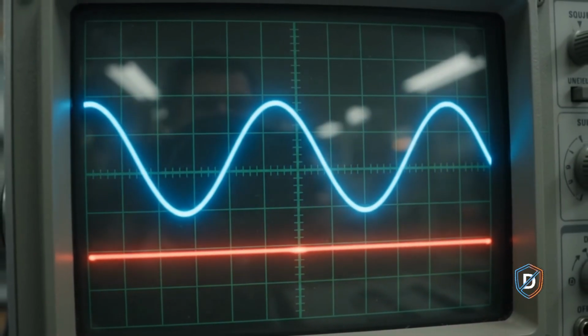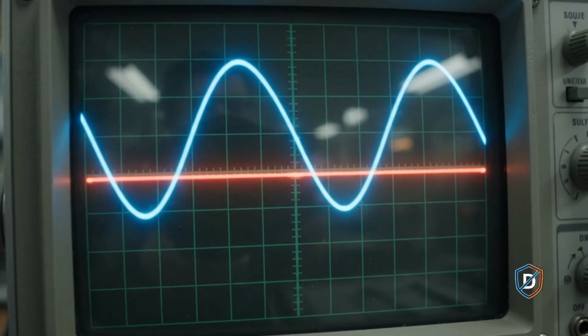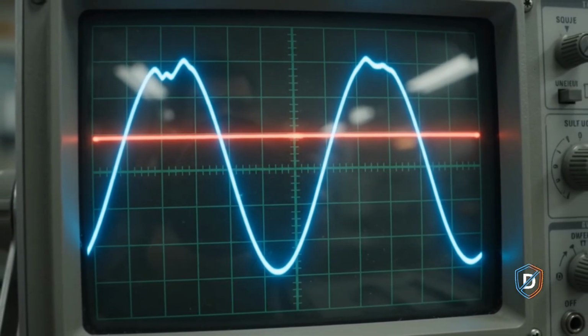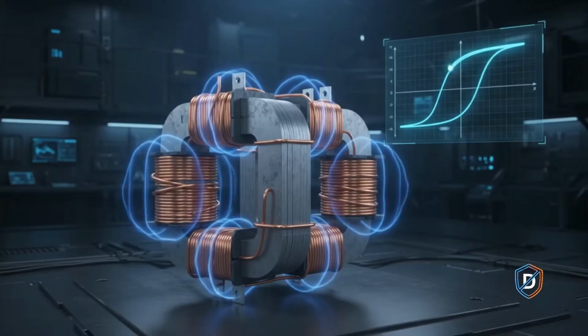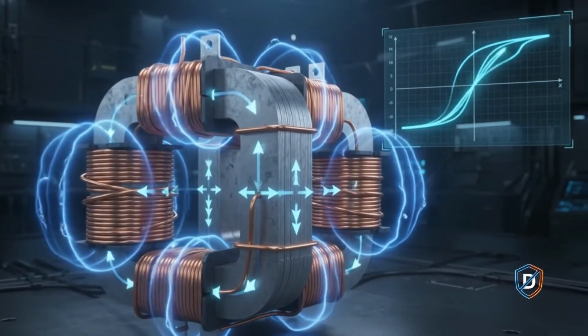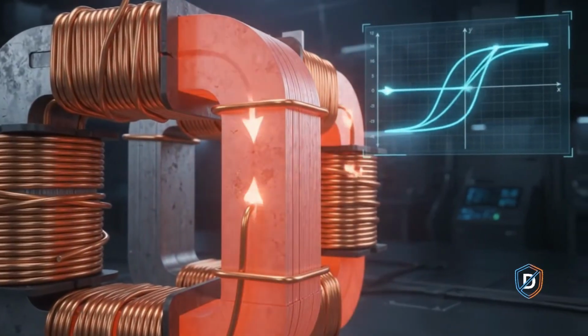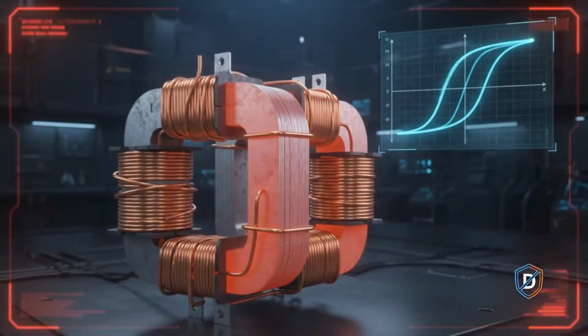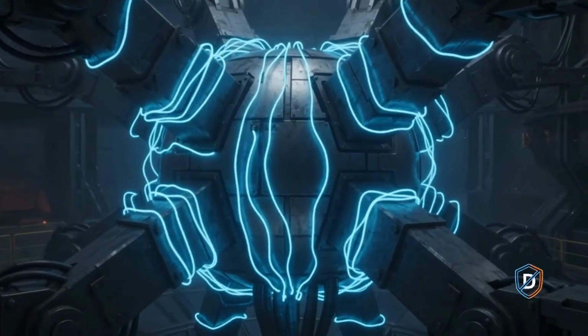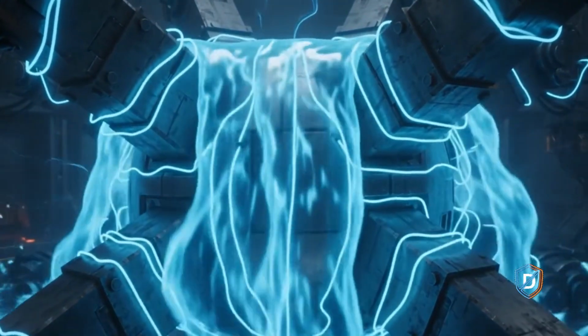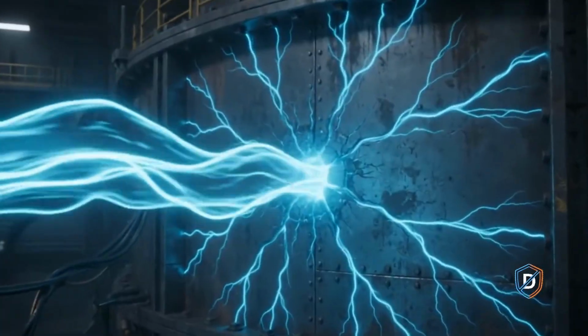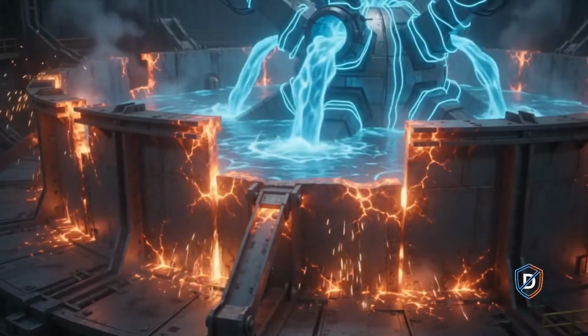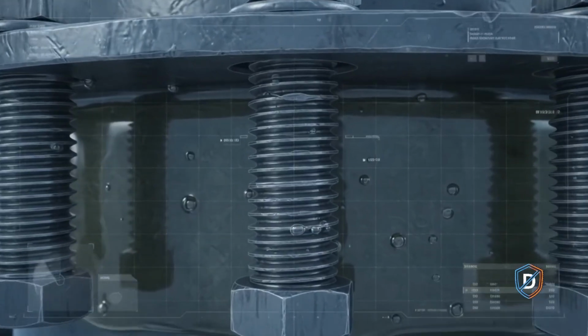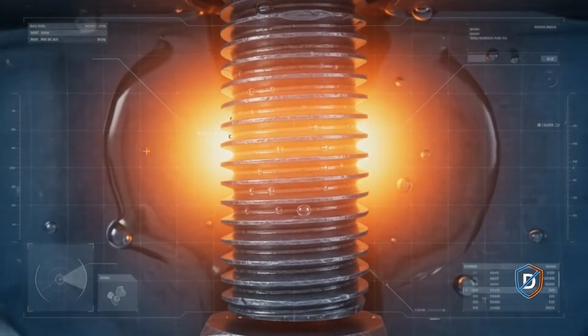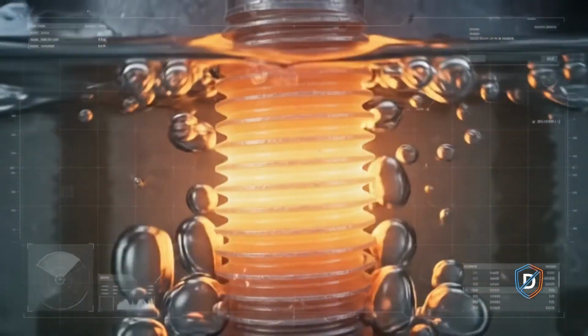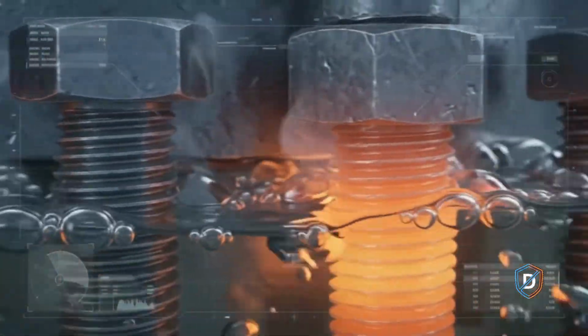When DC mixes with grid AC power, it shifts the entire operating wave off its zero axis. This DC bias forces the steel core into magnetic saturation during half of every single power cycle. Unable to carry more magnetic energy, the saturated core spills raw flux out into structural tank walls. The steel tank becomes an accidental induction heater, scorching surrounding oil within minutes.